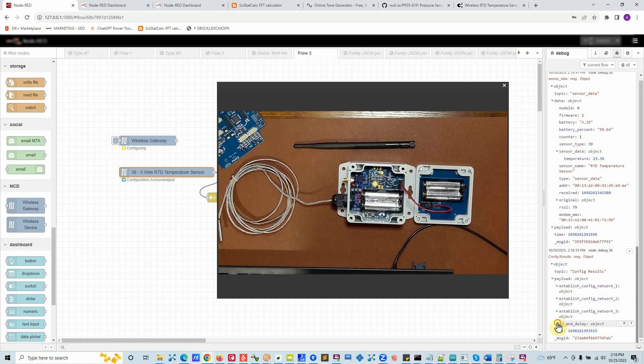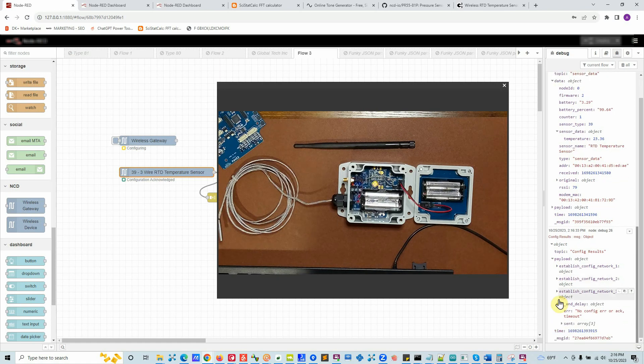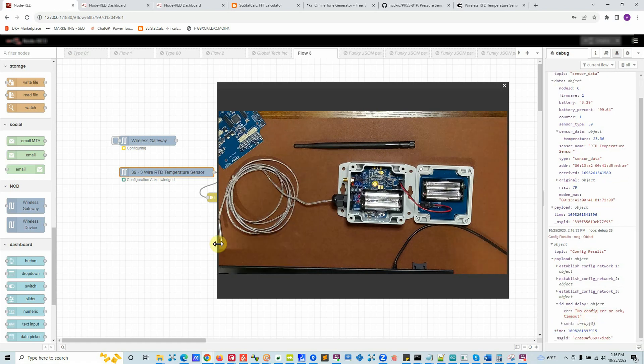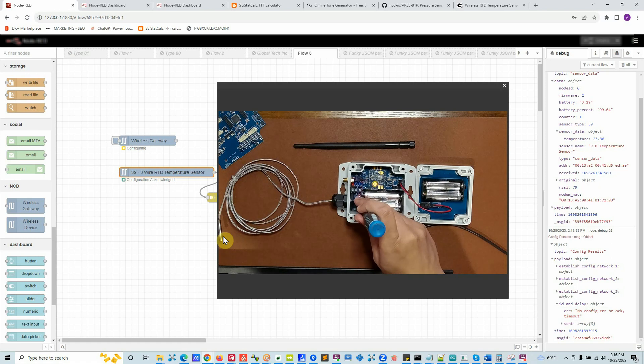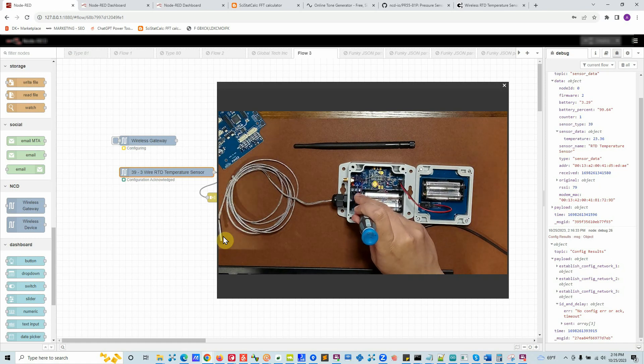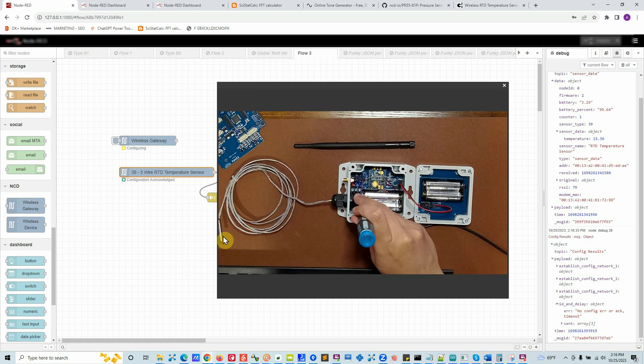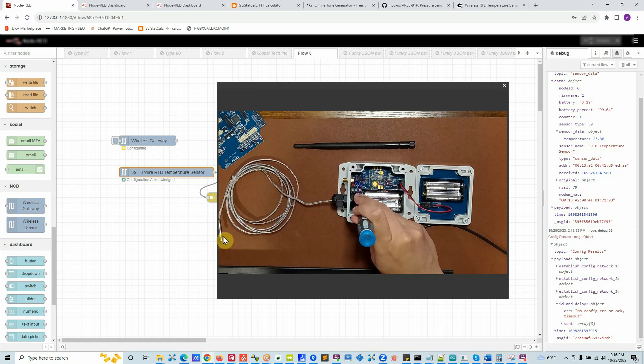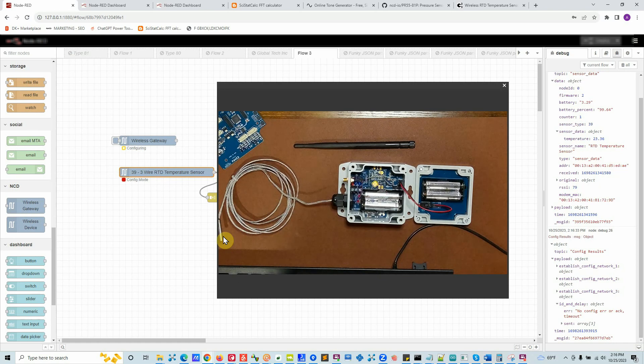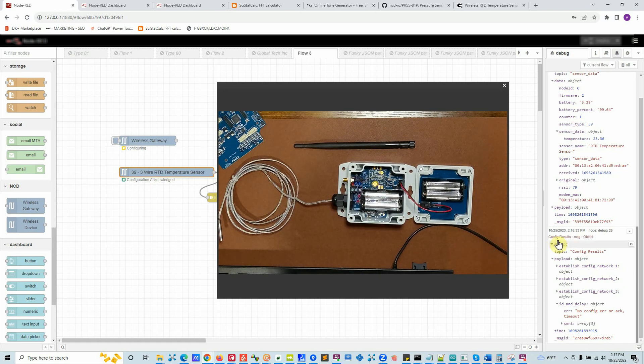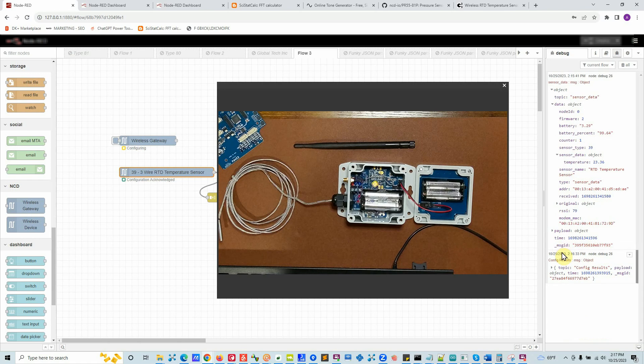Once the configuration completes - as you can see configuration completes - the configuration did not go through this time. We should have seen true here. So what you will do is again you will press and release the R button, immediately hold the config button for 10 seconds. Once that will send the config message again, config acknowledged, and we'll wait for the config results message.